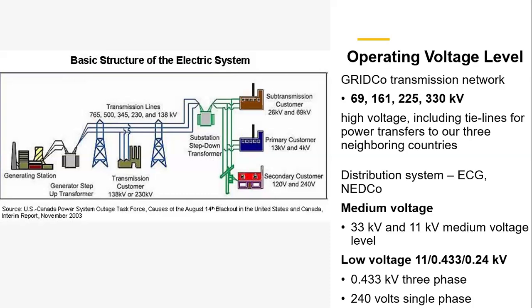Now, most of us are put onto the residential load levels. In Ghana, we have two main categories. We have the Ghana Grid Company, which is a high voltage transmission system, operating at 69, 161, 225, 330 kV, including tie lines to the three neighboring countries. On the distribution side, we mainly have ECG and NEDCo, and I think Enclave Power is also there. They all operate on what we call medium voltages and low voltages.